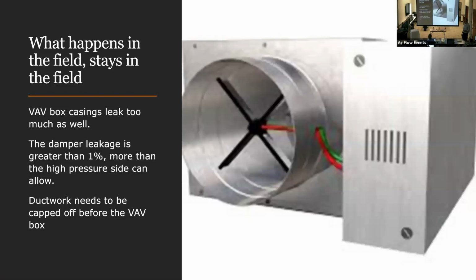Okay, terminal boxes. Do terminal box casings leak? What agency does the testing for terminal box casing leakage? Manufacturer? None, there is none. There is no test for casing leakage. Some manufacturers have a certified low leakage casing box, or you get what you get.